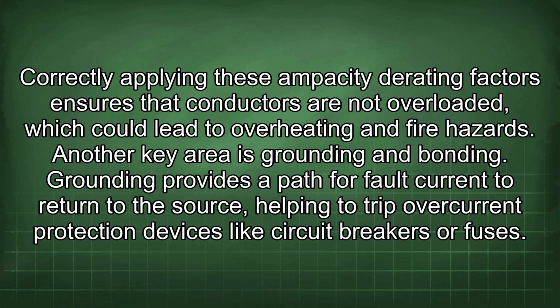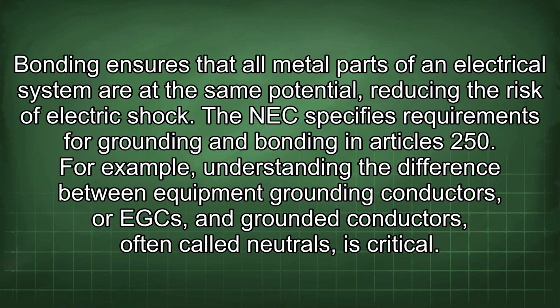Another key area is grounding and bonding. Grounding provides a path for fault current to return to the source, helping to trip overcurrent protection devices like circuit breakers or fuses. Bonding ensures that all metal parts of an electrical system are at the same potential, reducing the risk of electric shock. The NEC specifies requirements for grounding and bonding in Article 250.